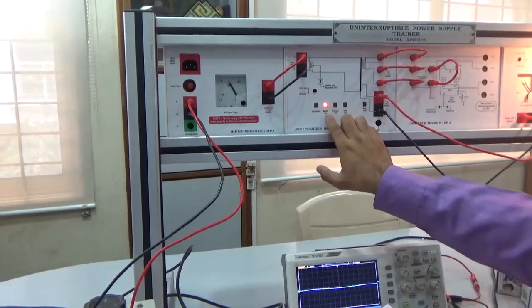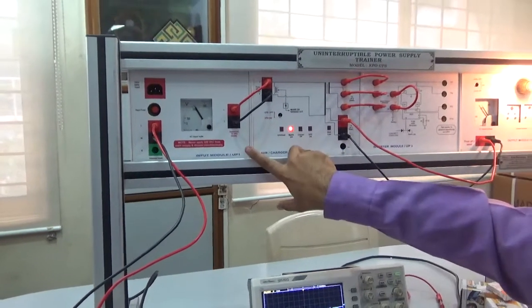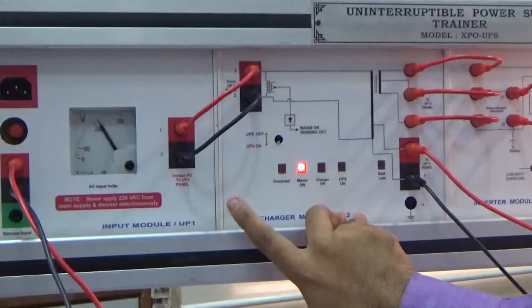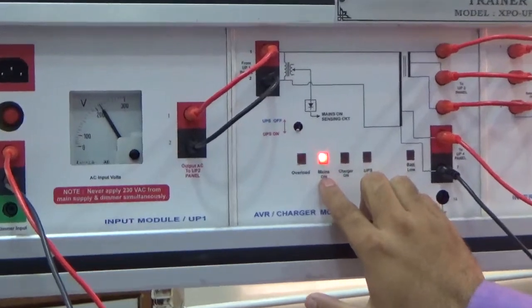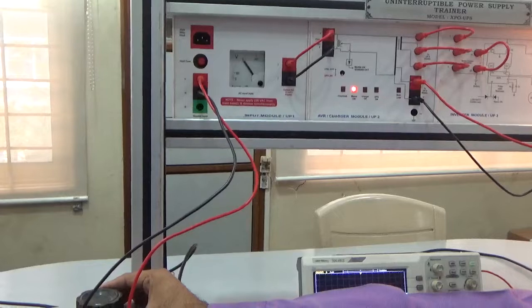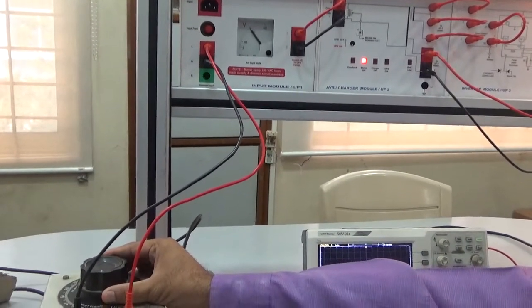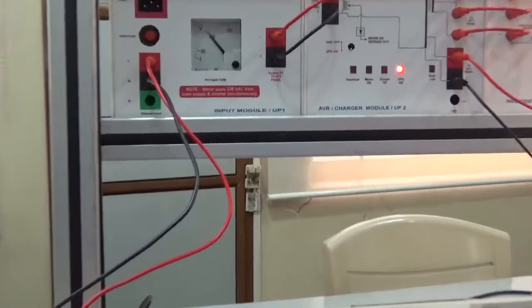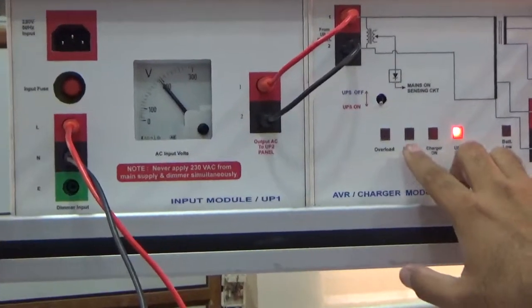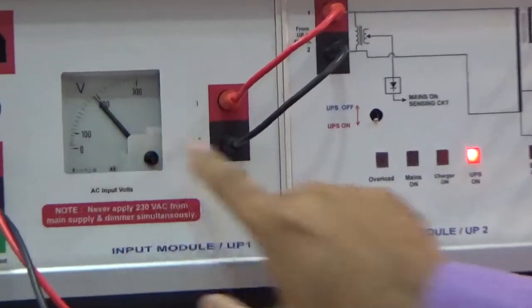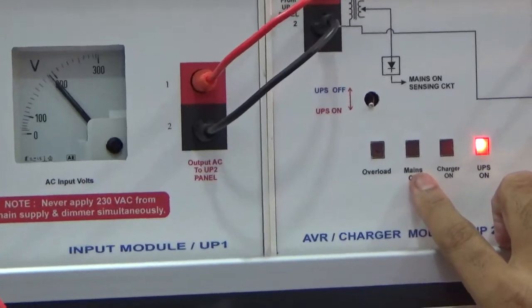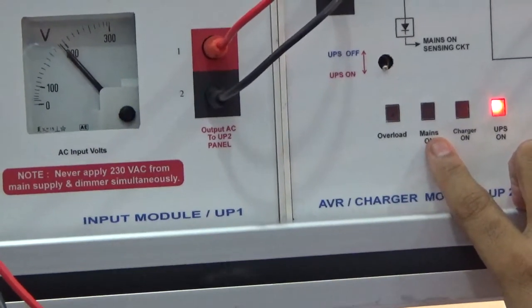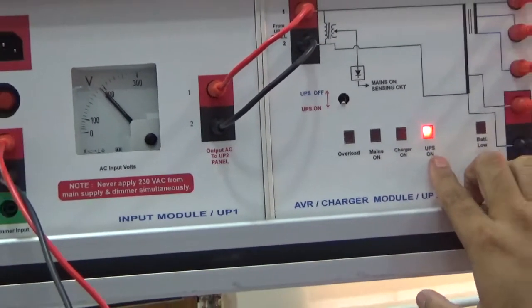210 volt is available and the under voltage setting is below 190 volt, so it is showing mains on. We are decreasing input voltage slowly. At 190 volt, here though mains is present, UPS changeover and turns to UPS on.